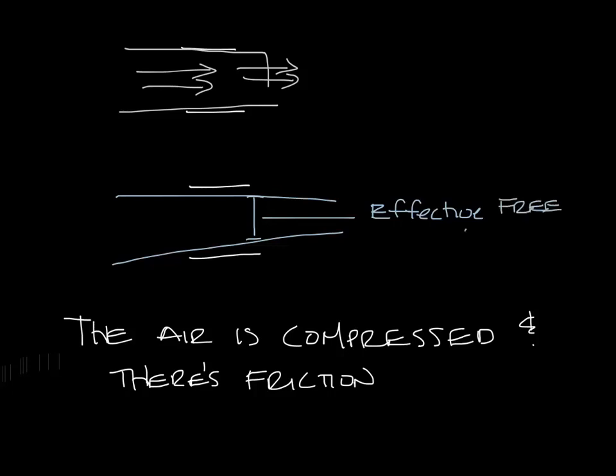So this is the effective free area. It's referred to as a sub k. So the equation becomes CFM equals a sub k times velocity. A sub k is something that the grill manufacturer has to calculate by measuring the airflow and face velocity in a lab.